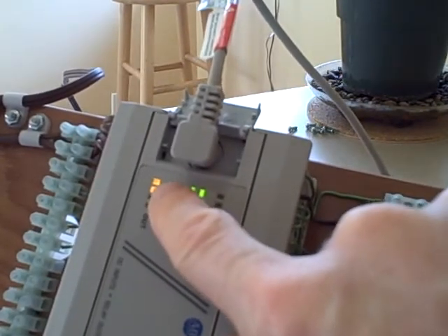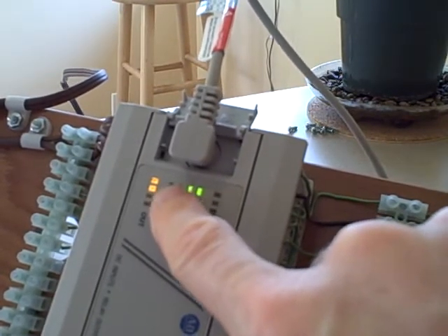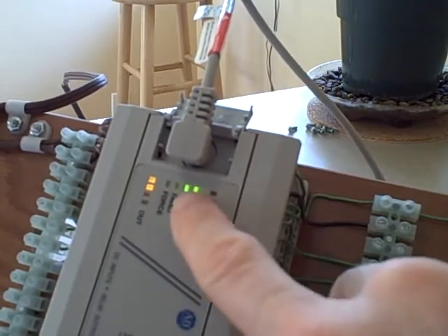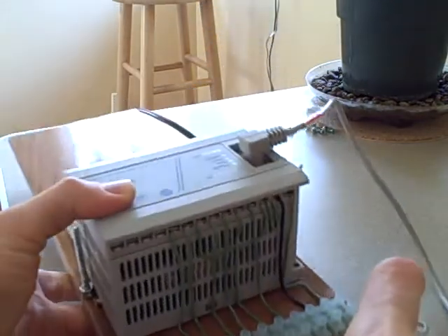If I enter the number 1 and press enter, you probably heard it click. That was the sound of that output discrete channel coming on. If I go over to the next bit and I enter a 1 there, you'll hear another click from the PLC. I've just turned on the first 2 bits of the output. If we look over here at the PLC itself, you see the first 2 discrete outputs are energized. That's because I just manually forced them to be a 1 status inside the processor.